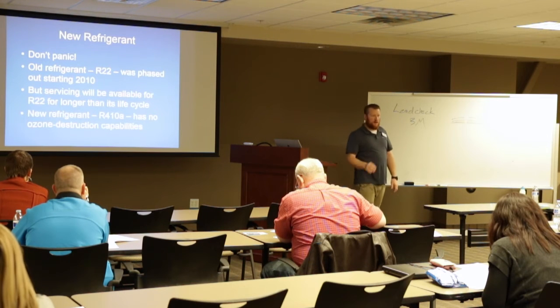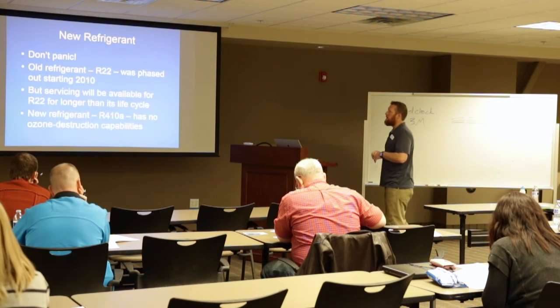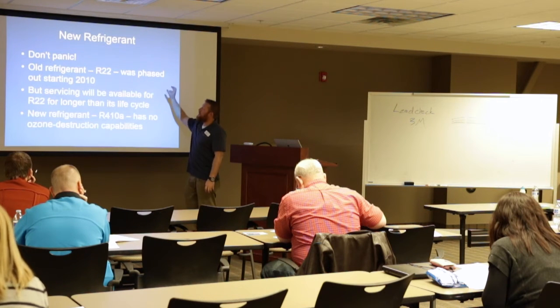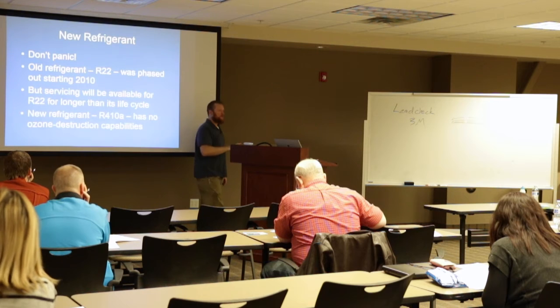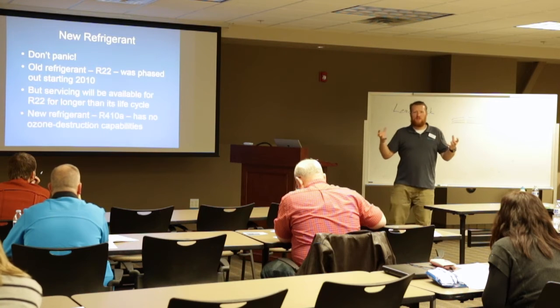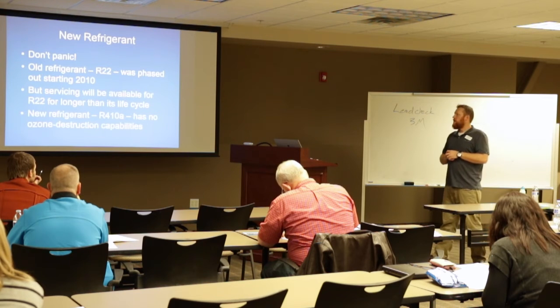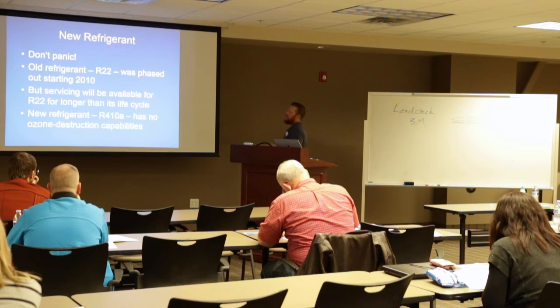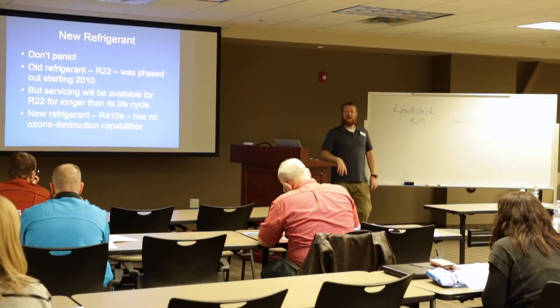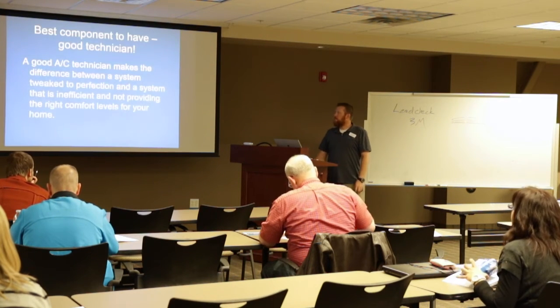There's a lot of other new refrigerants, that's another technology change that happened 6-8 years ago, where they stopped doing the R22 because it was bad for the ozone and causing environmental issues. You can still do that. They won't manufacture any parts. So if you have an older air conditioner built, probably 10, 15 years or older, just know that a lot of those components might not be available, but they can still recharge it, they can still service it. All the new ones now have the R410A. Puron, I think, is one of the proprietary blends of it, but it's all the same thing, it's all R410A, safe for our environment.